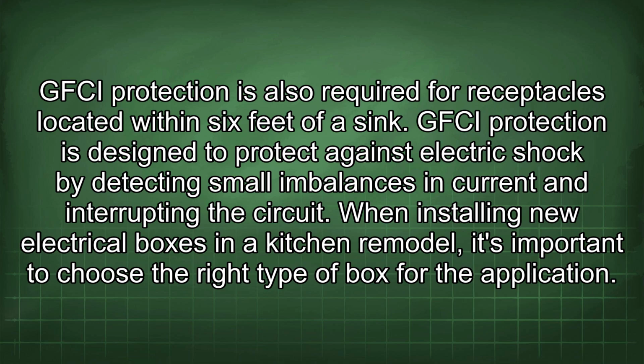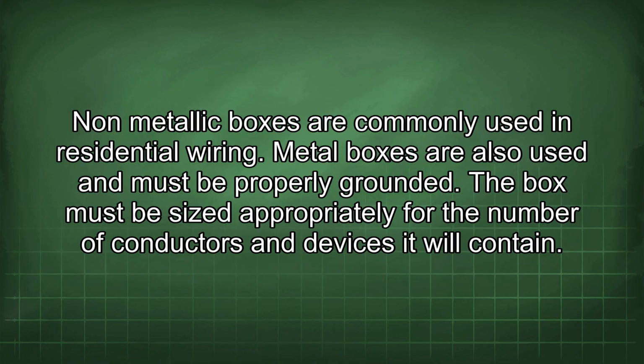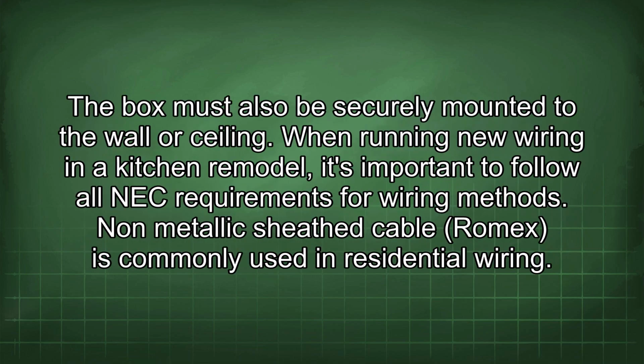When installing new electrical boxes in a kitchen remodel, it's important to choose the right type of box for the application. Non-metallic boxes are commonly used in residential wiring. Metal boxes are also used and must be properly grounded. The box must be sized appropriately for the number of conductors and devices it will contain. The box must also be securely mounted to the wall or ceiling.